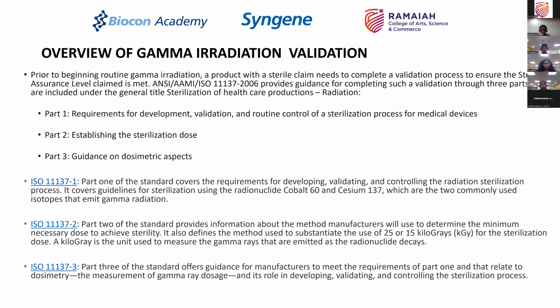Part 3 of the standard offers guidance for manufacturers to meet the requirements of part 1 that relate to dosimetry, which is the measurement of the gamma ray dosage and its role in developing, validating, and controlling the sterilization process. So this is more for the gamma ray dosage measurement, which could be at the end where the gamma irradiation process is done in the tunnel, or when you have the product coming out and you want to measure what was the gamma ray dose it was subjected to, and what is the residual radiation. Then part 3 covers the guidelines for this.